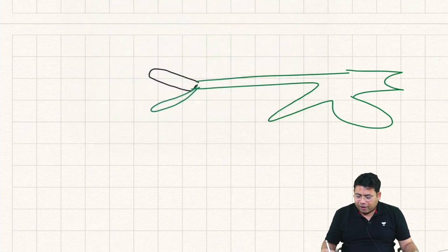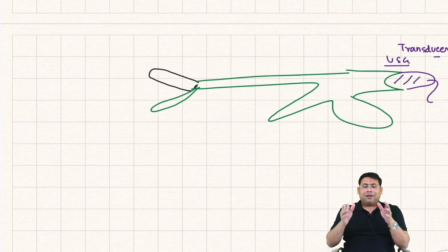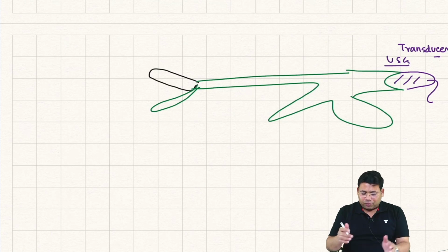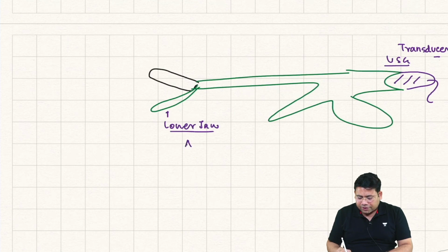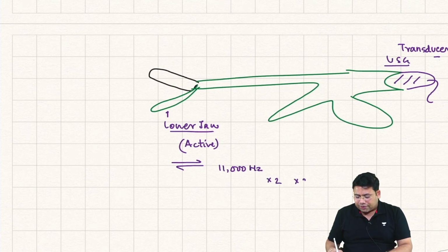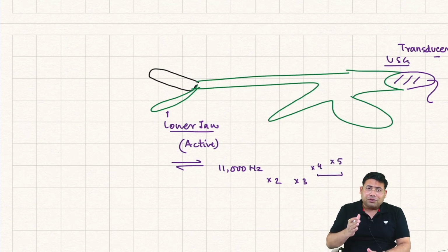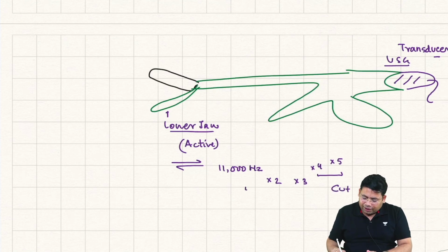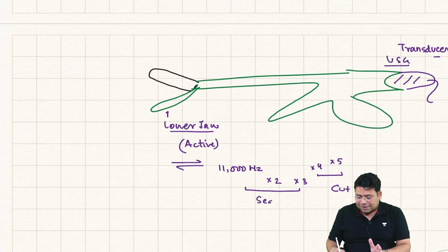We have a cavity behind, and through this cavity the ultrasonic, the USG transducer is connected. So when we talk about the USG transducer, this is the transducer which will actually give the vibrating energy to this. So this is the lower jaw, and the lower jaw is always remembered as an active jaw. So the active jaw has forward backward vibrations in the frequency multiple of 11,000. So it can be 2, 22,000, it can be 3, 33,000, it can be 4, 44,000, it can be 5, 55,000. Remember, at 4 and 5 the vibrations are so rapid that it can cut, and at 1, 2 and 3 it can seal. So this is very important.